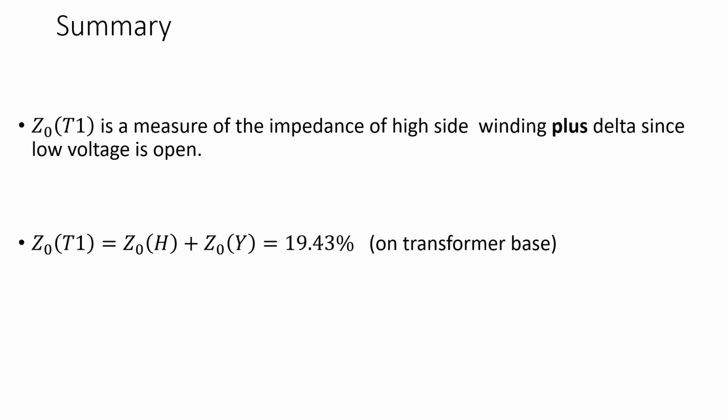So basically what you do, you start with the high voltage, you apply voltage to the high voltage. After you short all the windings, low voltage you leave open. Then you apply voltage to the high voltage windings being shorted, low voltage you short.